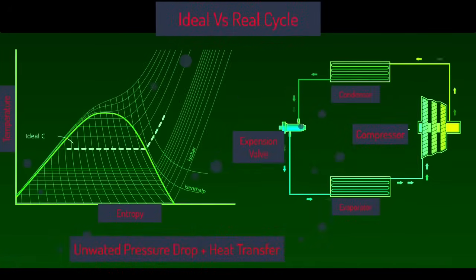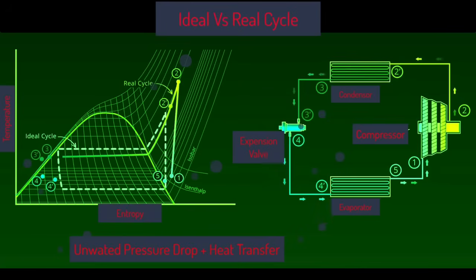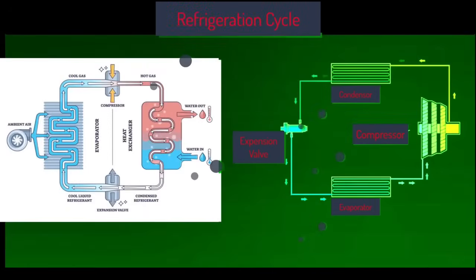In theory, the vapor compression cycle follows a clean, ideal path on thermodynamic diagrams. But in practice, the actual cycle deviates from the ideal, primarily due to irreversibilities like pressure drop associated with fluid flow through the pipes and system components, and heat transfer to or from the surroundings. These effects reduce the system's overall efficiency and shift the cycle path away from the ideal curves on PH or TS diagrams. Understanding the refrigeration cycle is essential for HVAC engineers as it allows them to evaluate the system performance across different operating conditions and applications. Whether you're sizing chillers, analyzing HVAC loads, or selecting refrigerants, this cycle is at the core of it all.